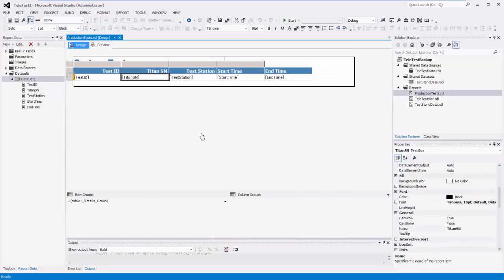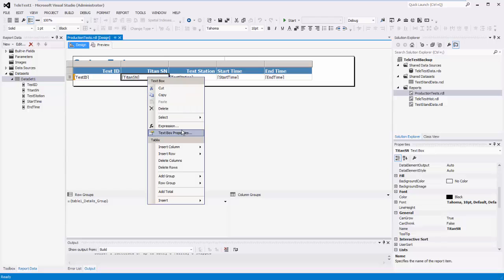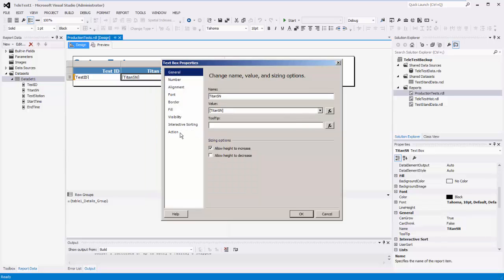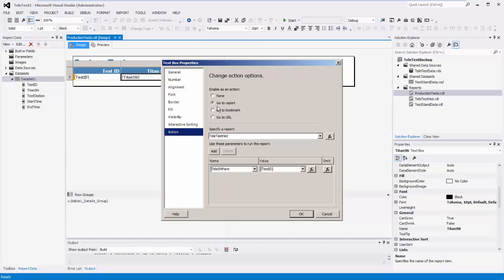The way we drill down into the more detailed report is by choosing the serial number field. When we choose this serial number, we pick a variable from the drop-down and it calls the other report. Looking at the text box property under Action, we have the option 'Go to Report.' That other report is specified here, and it passes in the parameter called test ID, which will be used in the next report to extract information from the Wonderware Historian.